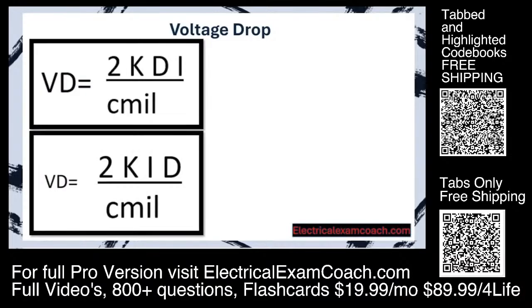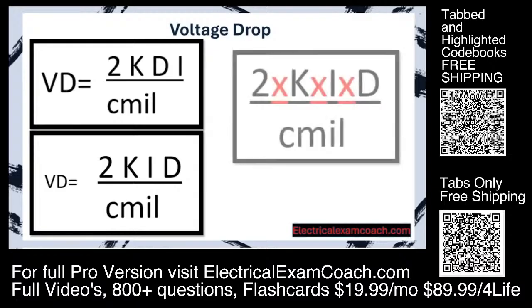I do it like this. 2KID over C mil. Easy to remember and easy to plug in. And what this is, just like previously in the program, this is implied multiplication. So it's going to be 2 multiplied by K, multiplied by I, multiplied by D, divided by C mils. Now let's learn what each one of these individual pieces mean.